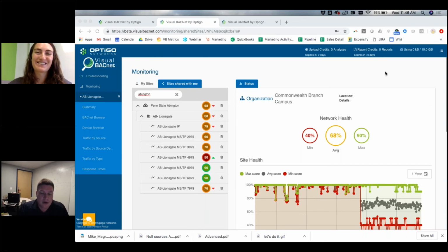No, not really. We have our Division 25 spec that we're currently revamping, trying to get rid of a lot of duplicate stuff. It's been so organic over the years that there are duplicate sections that don't match up and have different requirements. Like one of our requirements is for mini switches. If we need a mini switch in a location for tech access, that doesn't mean plug all the rest of the panels on that same wall into that mini switch. We want to eliminate single points of failure as much as possible. But yeah, we're slowly getting the specification to where we want.